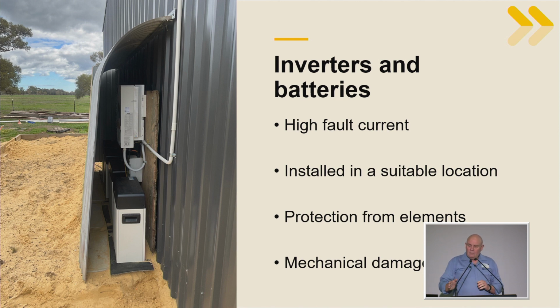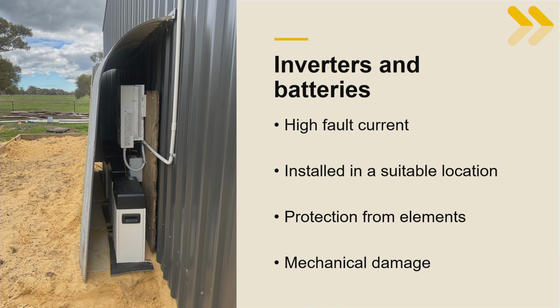But a system like this, a small system, you can have about 20,000 amps worth of fault current. If something goes wrong with the batteries in a small system just like this, it's the equivalent of dropping a spanner across 200 car batteries all at once.